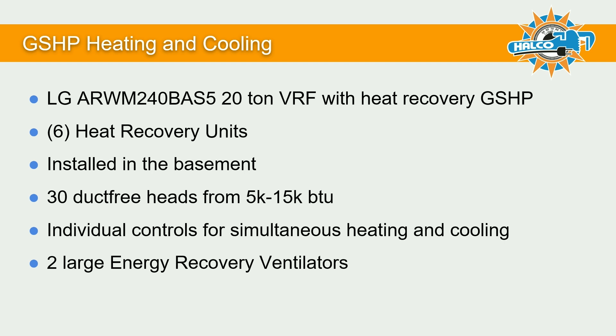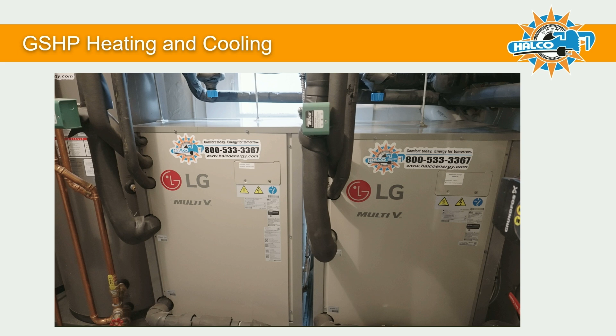Individual controls for simultaneous heating and cooling, and that's the whole idea. If we're going to have a bed and breakfast, if we're going to have multi-use rooms, some people are going to want heating, some people are going to want cooling, and then of course we don't want to waste any of that. So with the heat recovery system, all that wasted heat that would otherwise be injected into the ground is also being used for domestic hot water. Those are the units themselves, 10 tons each.